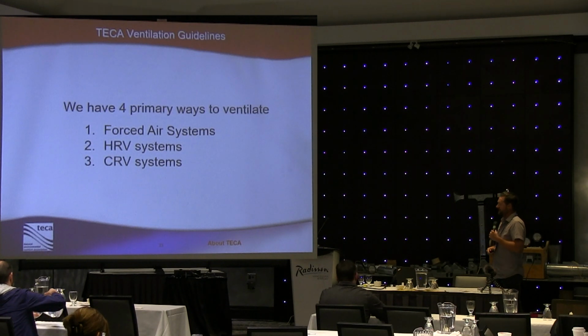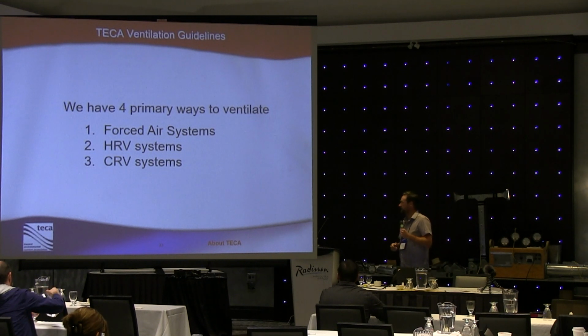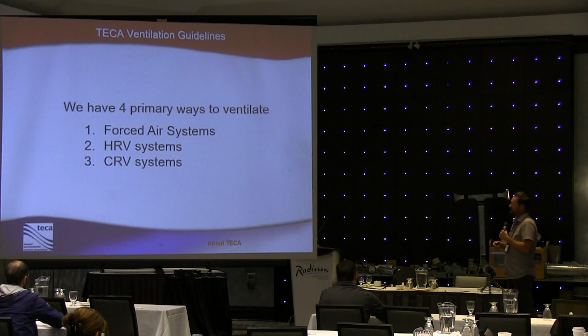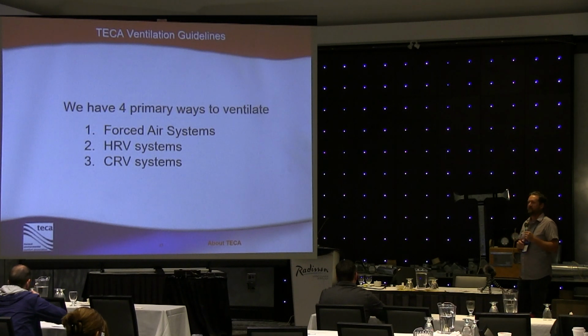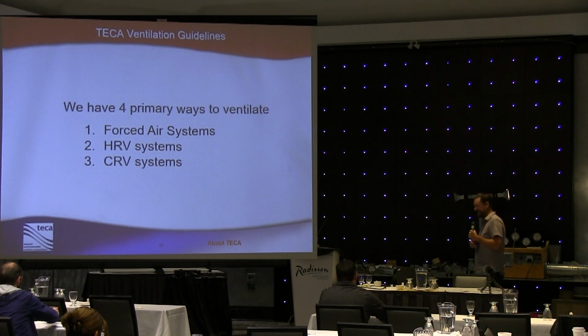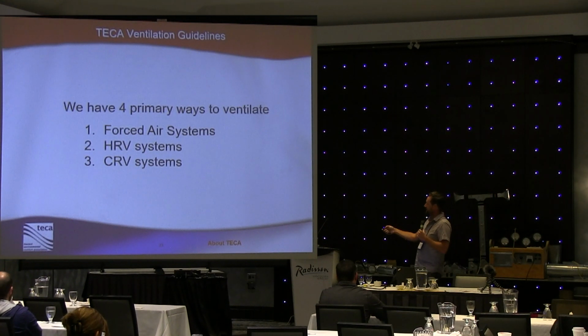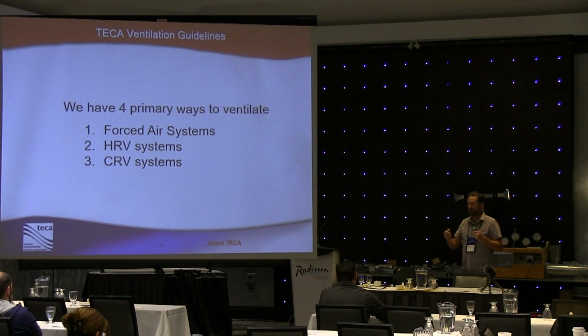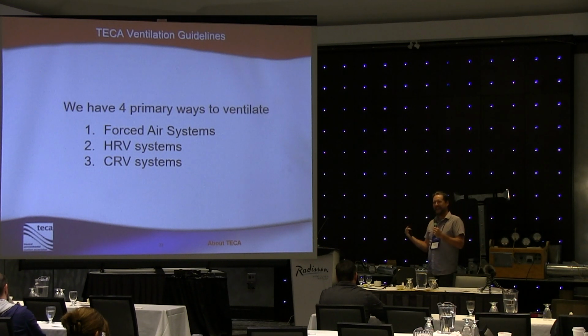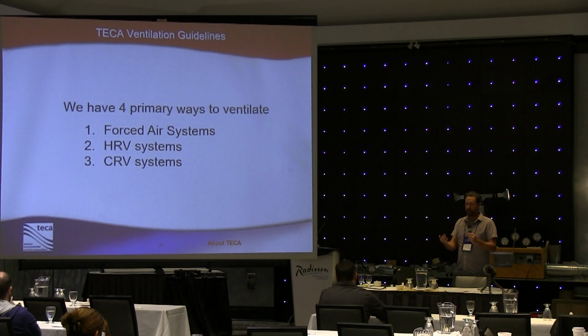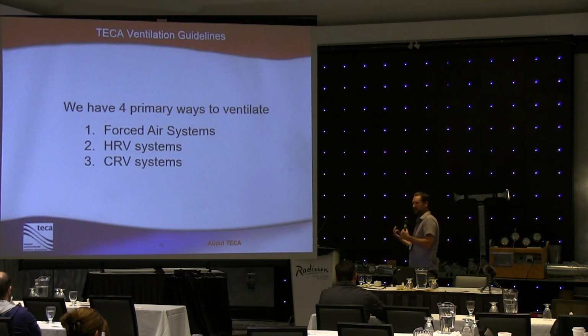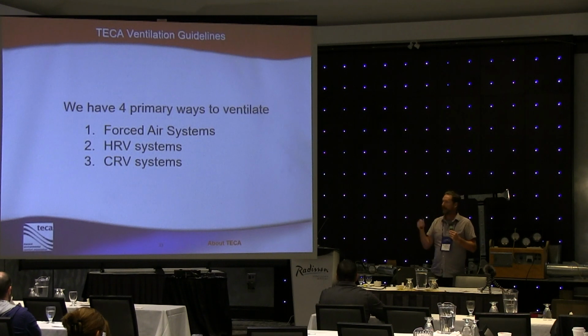We also have systems called CRV systems, and this is a central recirculation ventilator. A CRV system is a little bit different than an HRV, in that it doesn't provide us really any method of extracting any heat energy from our exhaust products. I'll step back a bit here. An HRV system, heat recovery ventilator, the beauty of it is that as we exhaust conditioned air that we've already paid to either heat or cool, as we exhaust that stale air from the building, the heat recovery ventilator can perform a function where it saves some of that energy. It'll actually take some of the heat energy out of that warm air that we're exhausting to the outside, and transfer that heat energy over into the fresh air that we're bringing back into the building. Fabulous setup, works really well.